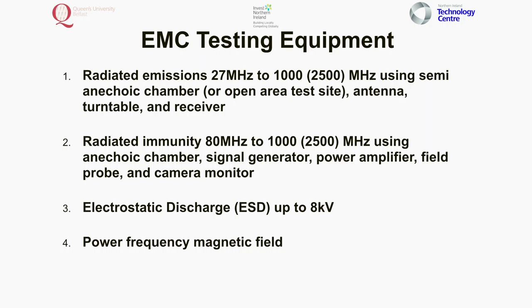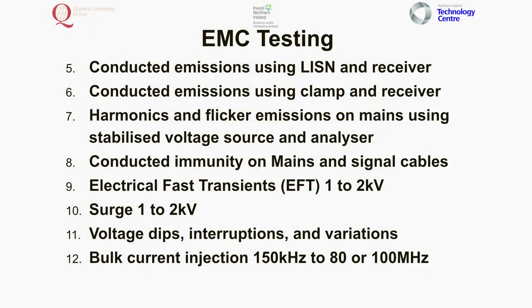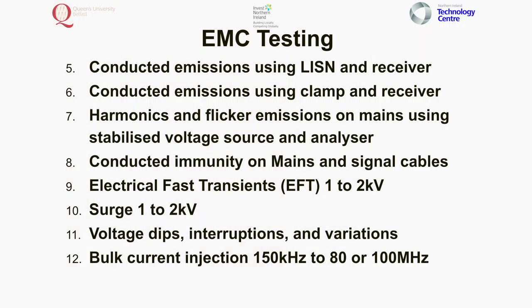There are something like 12 tests a product might have to be subjected to. Battery-powered equipment might only require three, but if it's mains powered it could be 12 tests. Radiated emissions cover the frequency range from 27 MHz to 1 GHz; the basic standard is now up to 2.5 GHz, and for some standards the requirement is to go up to five times the highest clock frequency — which could be up to 6 or even 12 GHz. Testing uses a semi-anechoic chamber or open area test site, with the antenna, turntable, and receiver.